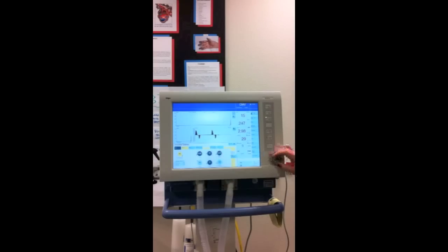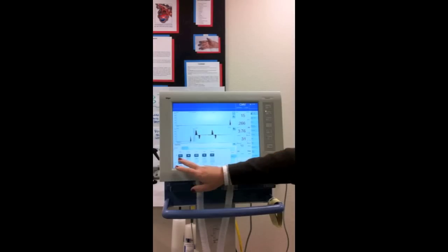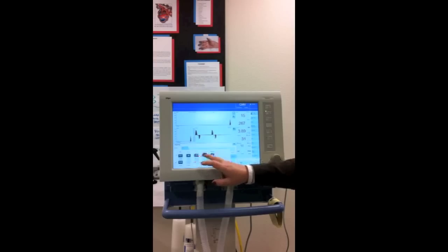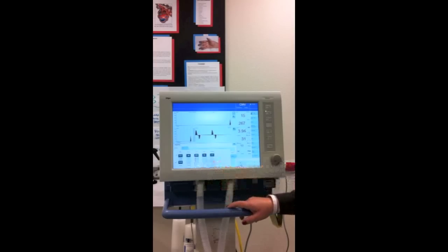So if we wanted to go down to 75, we push it. Bless you. Thank you. And then go down to 75 and then hit confirm. Now it will take it. This is the confirm button. So our alarm silence, this is where we can set our alarms. This one just has high minute ventilation, low minute ventilation, high pressure, inspiratory time, high tidal volume, high rate, and apnea. Those are the only alarms on this ventilator.